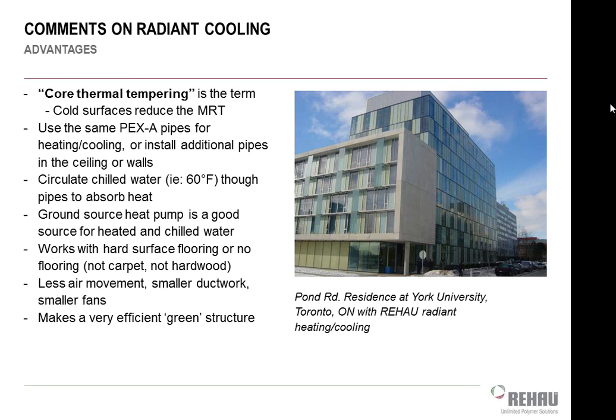The idea there is similar to what we do on the heating side on these larger commercial buildings. We're just trying to take care of the base thermal cooling load of the building. The latent is still handled by an air handler, and sometimes you might need some additional cooling sources at the perimeter if you have not done a good job with your windows and insulation and things like that. If it's a new building built to current standards, you should be able to cool the entire building with the radiant cooling panels in combination with the ventilation latent air handler.